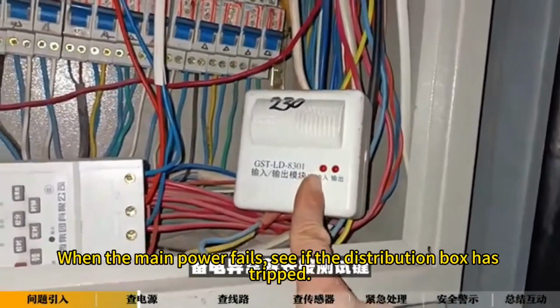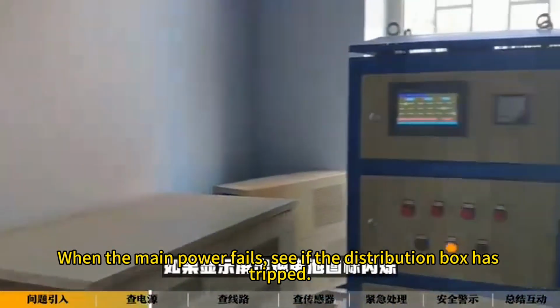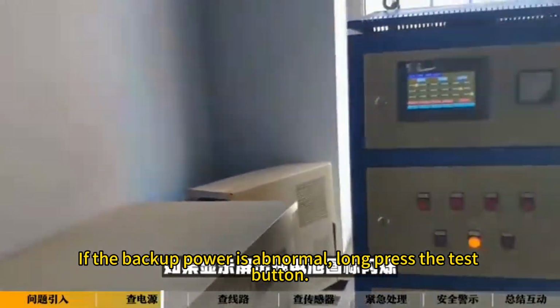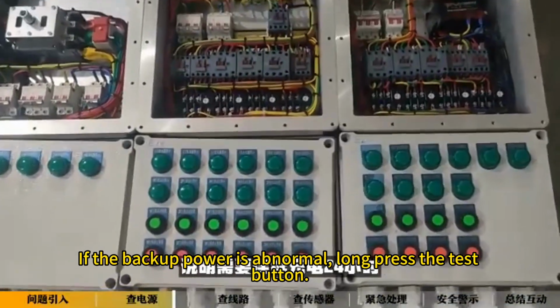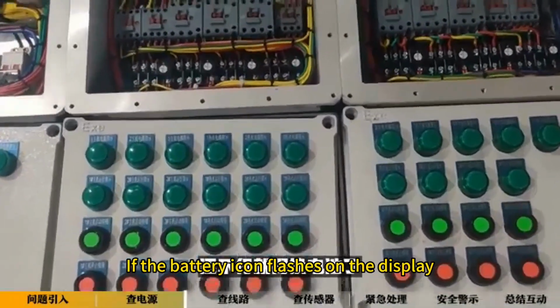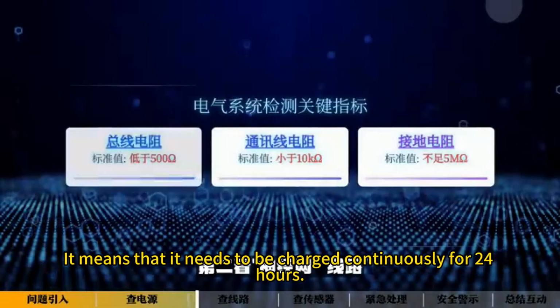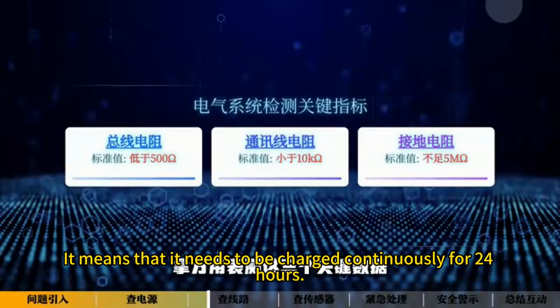When the main power fails, see if the distribution box has tripped. If the backup power is abnormal, long press the test button. If the battery icon flashes on the display, it means that it needs to be charged continuously for 24 hours.